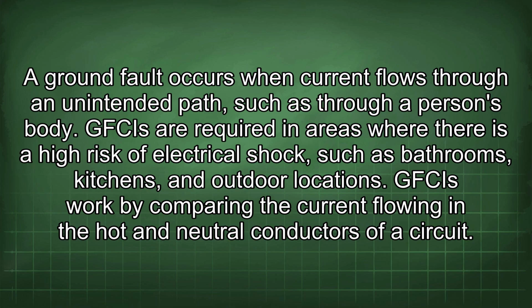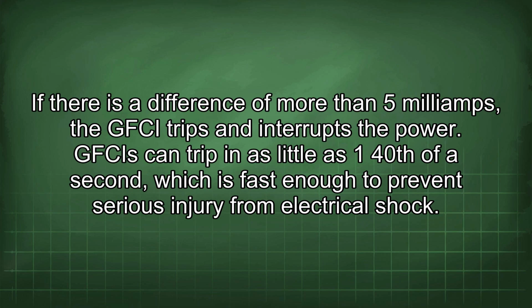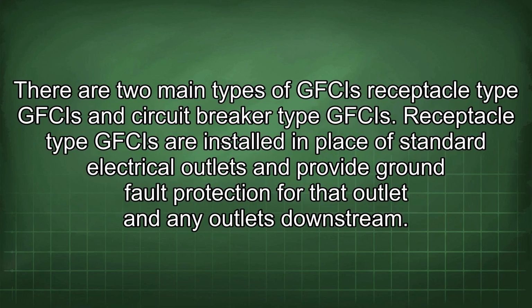GFCIs are required in areas where there is a high risk of electrical shock, such as bathrooms, kitchens, and outdoor locations. GFCIs work by comparing the current flowing in the hot and neutral conductors of a circuit. If there is a difference of more than 5 mA, the GFCI trips and interrupts the power. GFCIs can trip in as little as 1/40th of a second, which is fast enough to prevent serious injury from electrical shock.